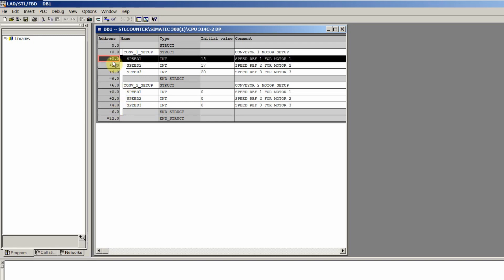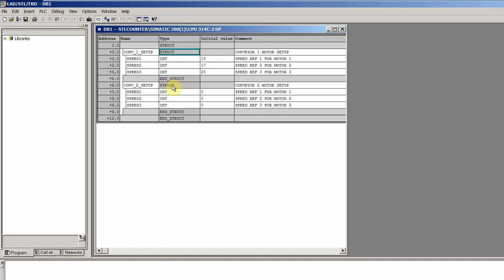Now there is a scenario where we have to send the speed references from structure one to structure two. This can be done using the move command, but the problem is that with the move command we have to send all the data one by one — for each speed reference we have to use the move command three times. To overcome this problem we will use the block move command, which we only need to use once and it will transfer our data from one structure to another at once.